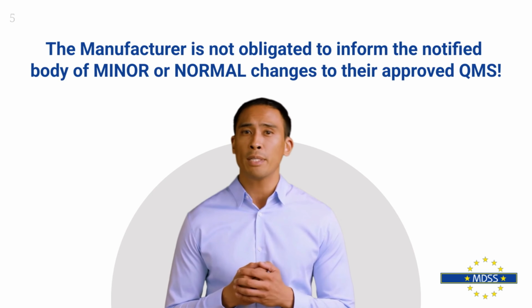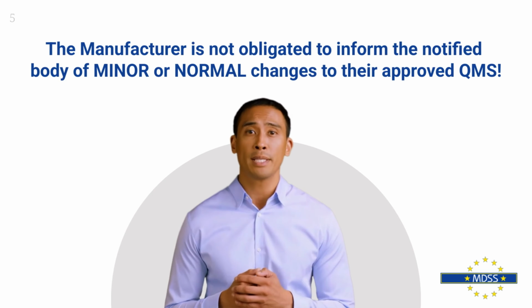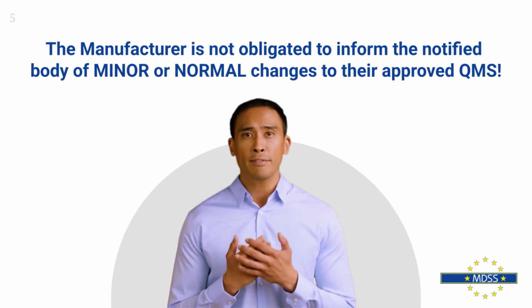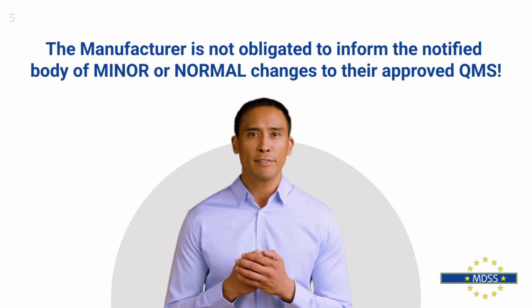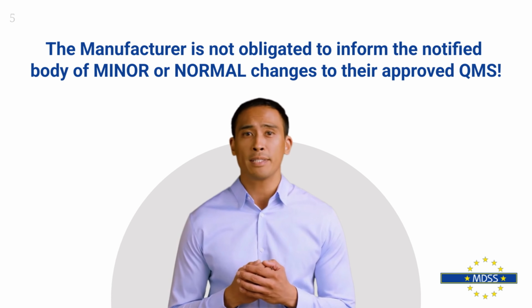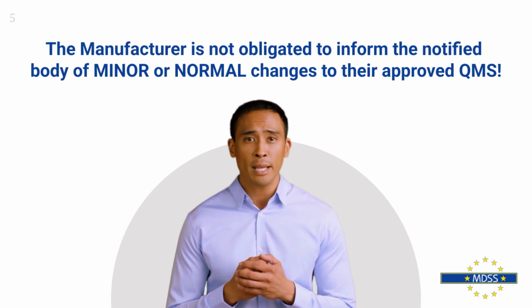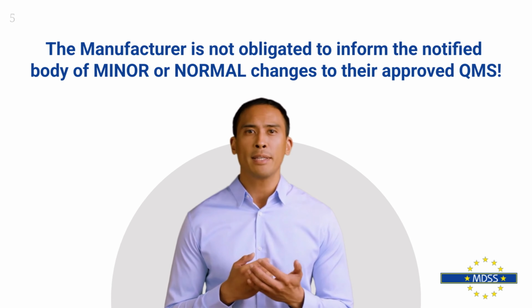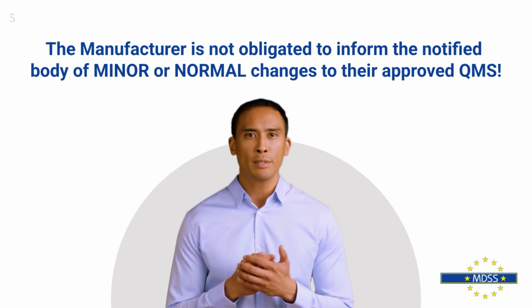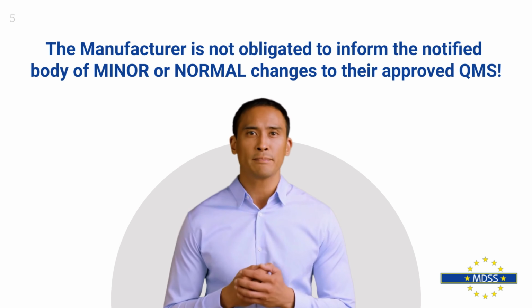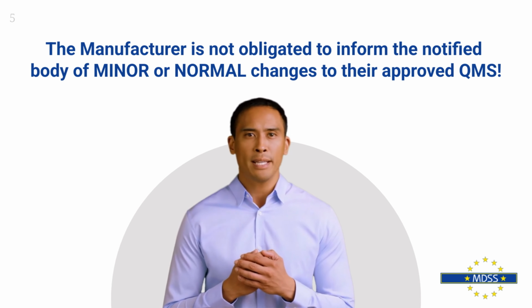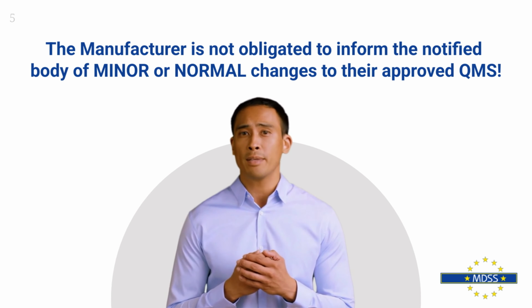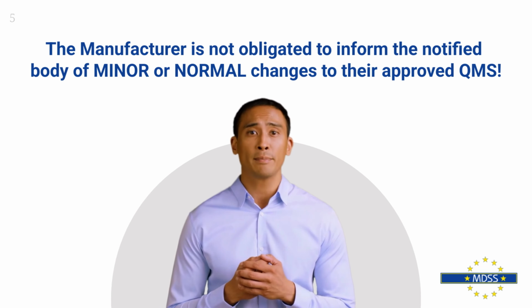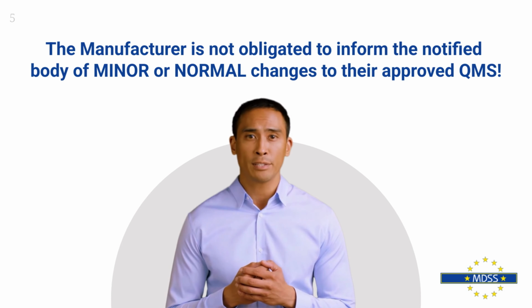It should be outlined which information is not required to be forwarded to the notified body. The manufacturer is not obligated to inform the notified body of minor or normal changes to the approved quality management system. Those changes may be implemented without informing the notified body, and those will not trigger a supplement to the certificate. This goes along with the common understanding that the manufacturer is responsible for the application of the approved conformity assessment procedure, which allows the manufacturer to act responsibly within the approved setting. Only substantial changes need to be approved.